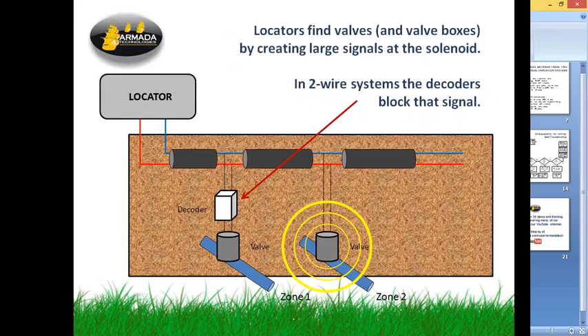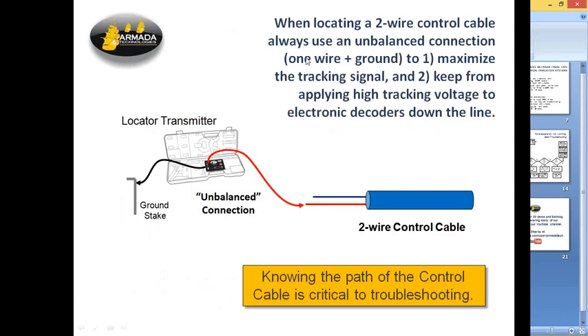Sometimes the valves are handy. They're just kind of along the chain. You follow the path of the wire, and you see the lids of the valve boxes. In a lot of places where the grass grows fast and landscape rock is used or something, they may be covered up. You may have to poke for them. You may have to use the TDR. Sometimes with experience, you can spot the valve box because it's got an extra little bit of coil of wire inside it, and the splice that's done there. So that's another way of finding them. But don't expect to find the valve boxes using a locator the way you usually do.